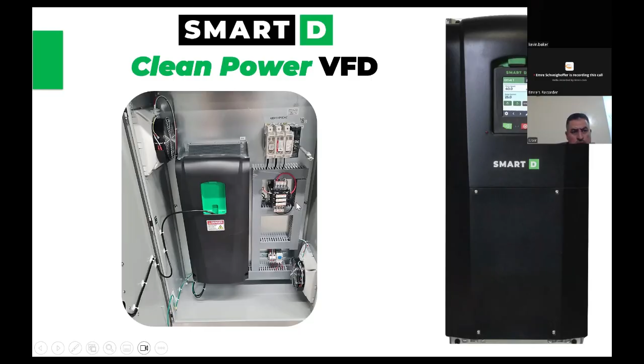That's good. All right. So the very first slide here, what I just want to look at this image over here, and we want to come back to this later. This here is a completely fully filtered drive. It looks like a VFD. We put it into a NEMA 4, NEMA 3R panel. But this has all the line and load filtering you'll ever need, all the advanced filtering, but you don't see any of the additional stuff. So we'll go through that in a second.